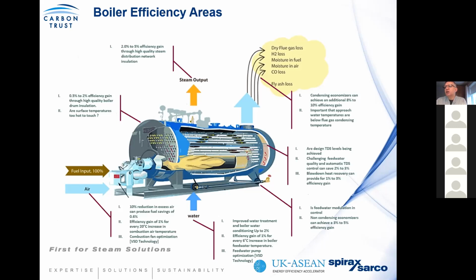A good indication of a good boiler house is a cold boiler house. The boiler should not be acting as a large radiator. We had case examples where we asked companies to remove the old insulation and reinstall new modern insulation, and in doing so noticed a marked reduction in temperatures within boiler houses. So in other words, if boiler surfaces are too hot to touch or handle, or are indicated as hot through a heat gun, there could be financial justification to re-insulate the boiler.